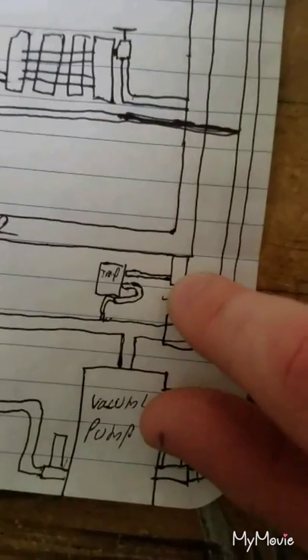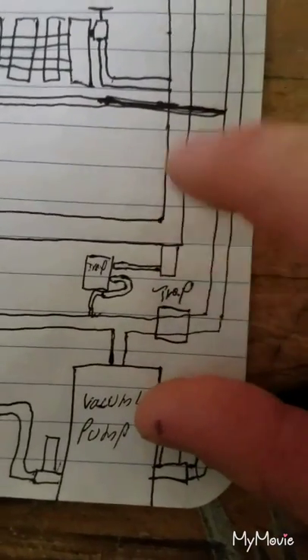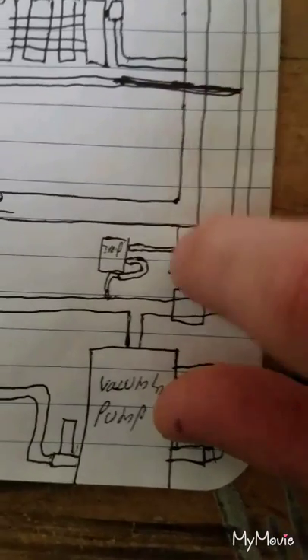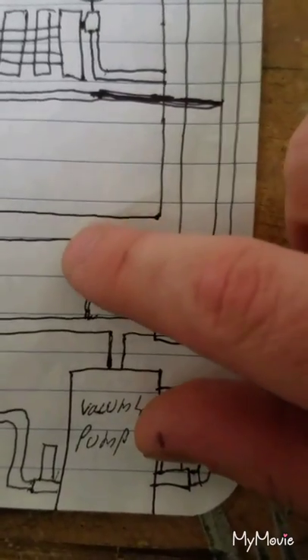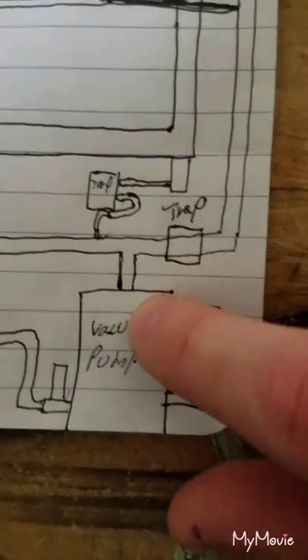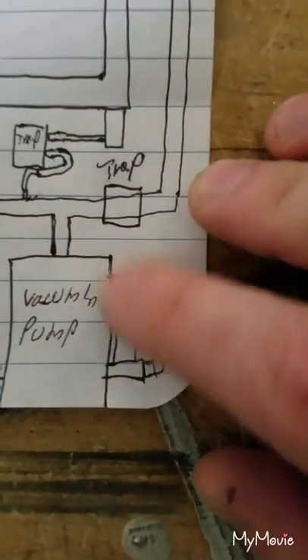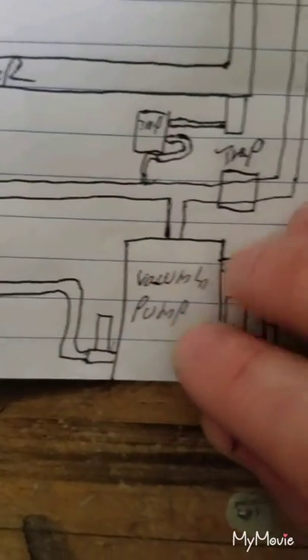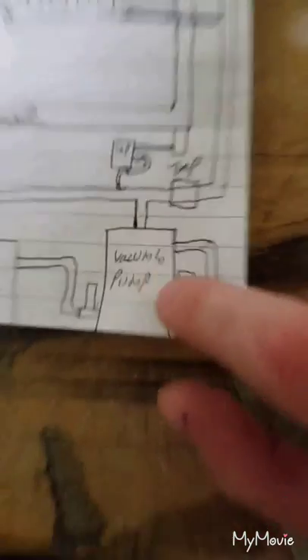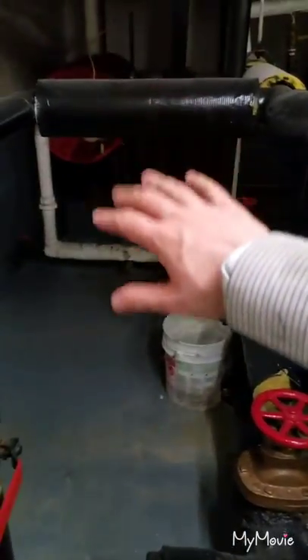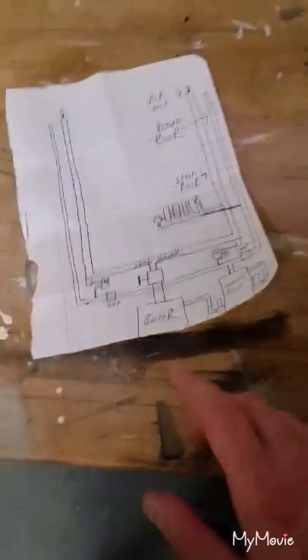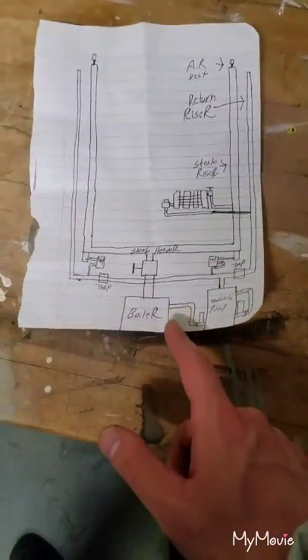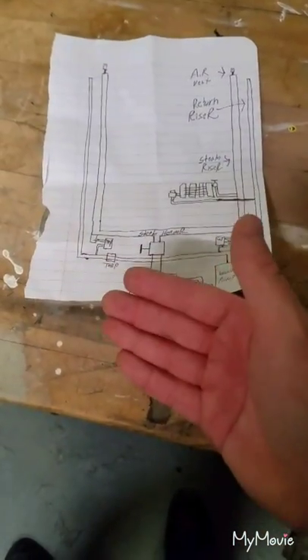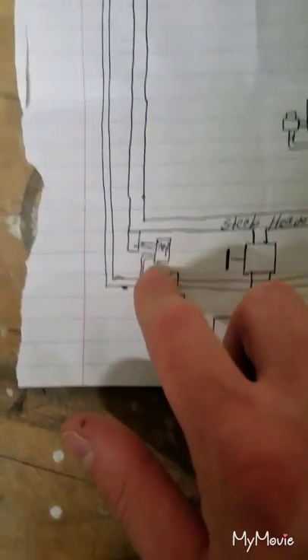The vacuum tank is pulling that condensate down. Now off the main steam header, you're going to have a trap and a drip leg, because there's still going to be condensate that'll form in here when the steam is going up, okay? So that condensate comes down the drip leg into a ball swing trap and back into the return line of the vacuum tank. These are the vacuum pumps that create the vacuum. These are the condensate pumps. In this case, instead of a vacuum pump pumping the condensate through a preheater and then into the sewer, if you have a boiler, it's going to pump it back as the boiler feed water, and the cycle is going to continue. Okay, it's the same deal on the other side.